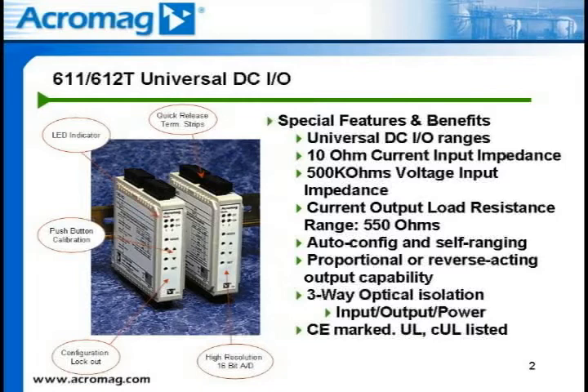Installation is quick and easy with the auto configuration and self-ranging features of the module. The internal microcontroller automatically senses the input source type, either voltage or current, and selects the optimum performance range for your 0 and full-scale input values. The push buttons on the front of the module are for adjusting to the desired output. This includes adjusting for a proportional or reverse acting response from the module. When the desired calibration is completed, simply press the Set button and the configuration settings are stored in the module's non-volatile memory.